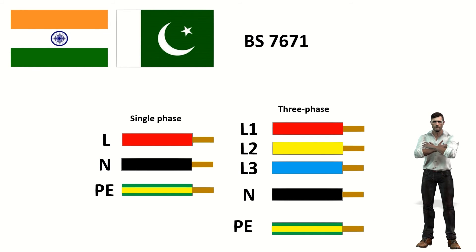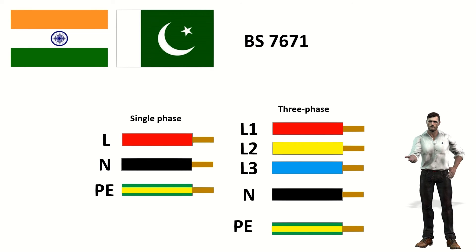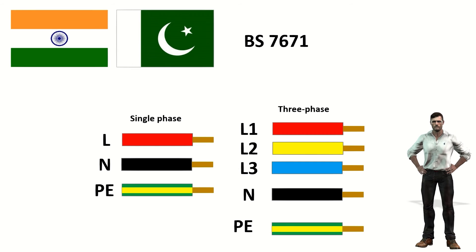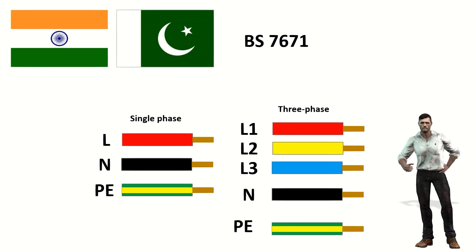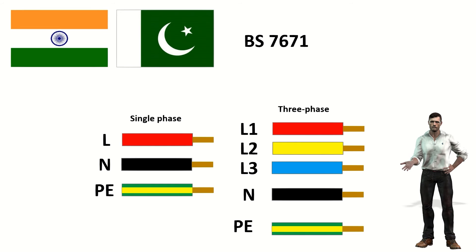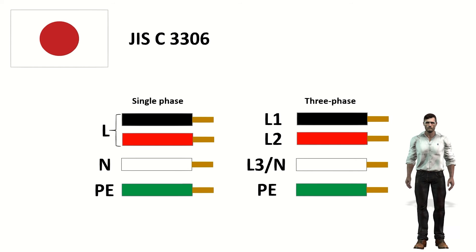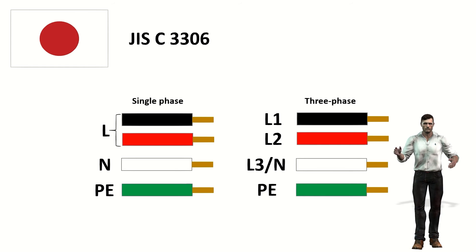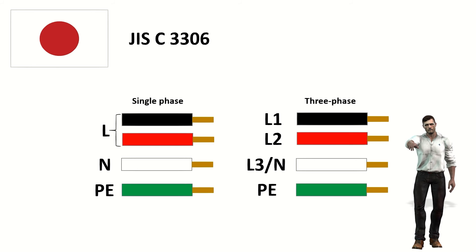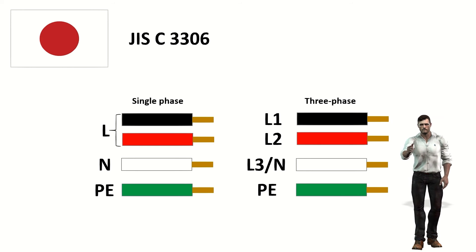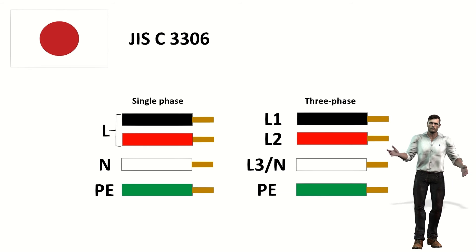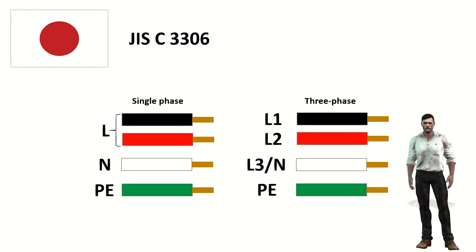Countries like India and Pakistan use the colors red, blue and yellow for the phases, black for the neutral, and green for the protection cable. This color code is in accordance with the BS7671 standard, which was also used in the UK until 2004, when they changed to the IEC standard. In Japan, single-phase systems use black or red for the phase and white for the neutral. The protective earth wire is green. In a three-phase system, for the phase cables L1, L2 and L3, the colors black, red and white are used respectively. White is also used for neutral in a single-phase two-wire system.